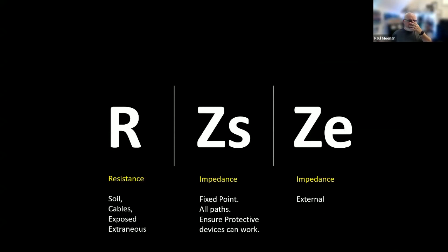Once we have those resistances checked and we energize our systems, we then look at impedance. Impedance being the sum total of resistances at a point. It's a fixed point. So you go to a socket, a light, a fuse box, and it does a test. It checks the resistance of all paths. And we want nice low impedances, because if we have low impedance, we then have lots of energy flowing to activate our protective devices.